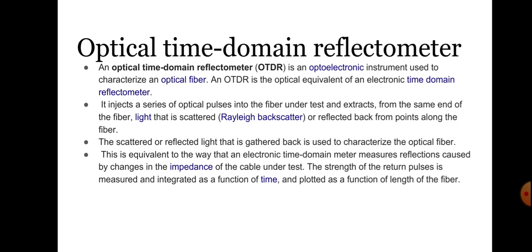The OTDR works on the principle of measurement of backscattered light rather than transmitted light. When we are experimentally finding a fault along the fiber, we need only one end of the optical fiber, which will be easily available.